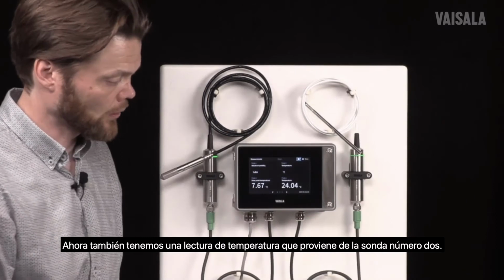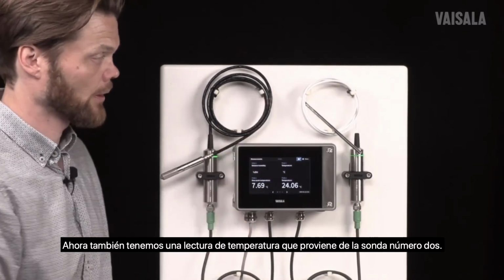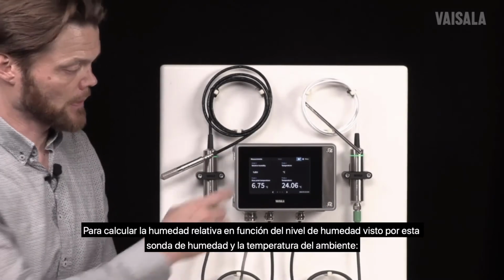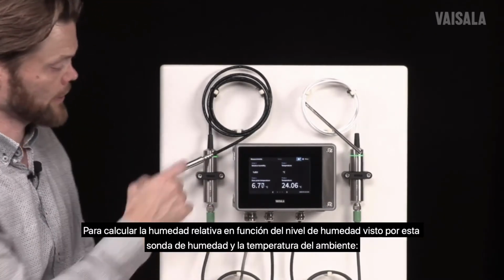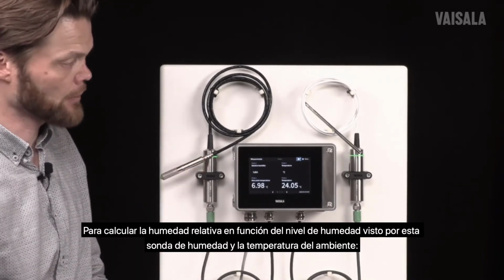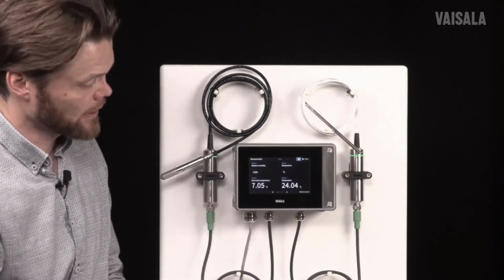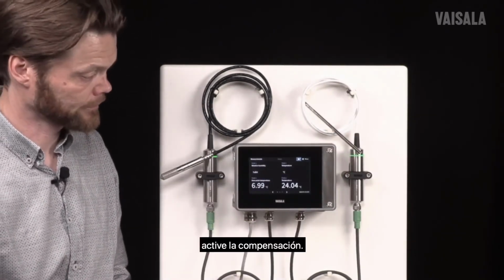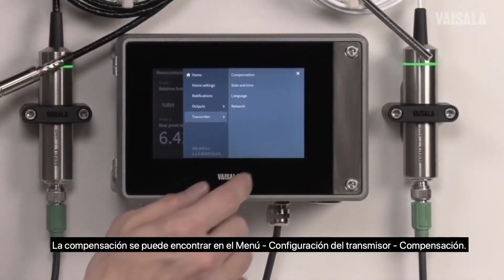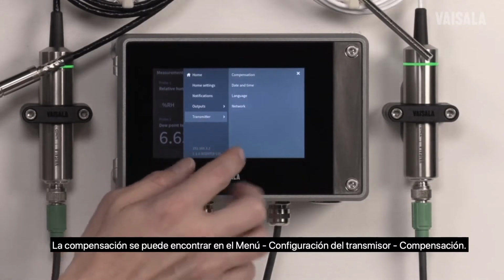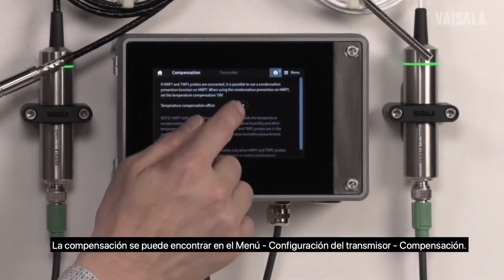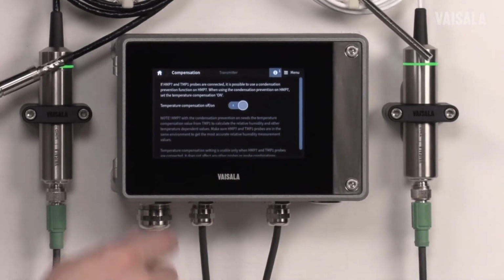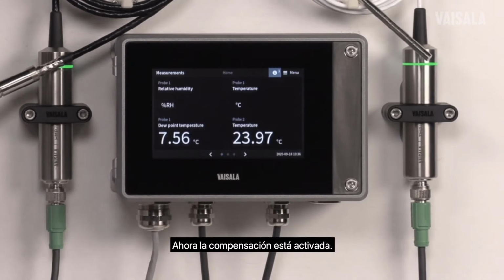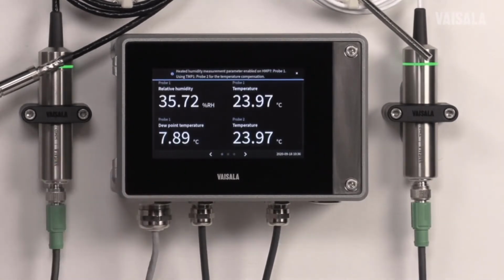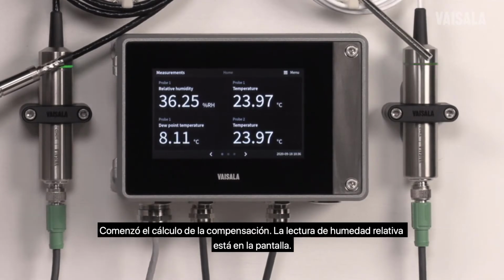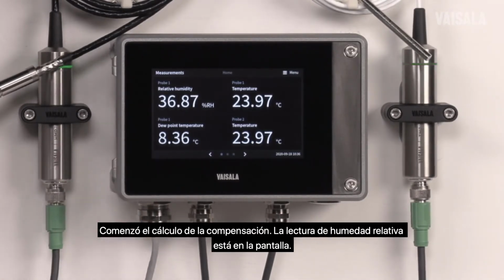And now we have also a temperature reading which is coming from the probe number 2. To be able to calculate relative humidity based on the humidity level seen by this humidity probe and the temperature of the ambient, we have to activate the compensation. Compensation can be found from the menu, transmitter settings and compensation, and now it's activated, and we can see that the compensation calculation started and relative humidity reading is on the display.